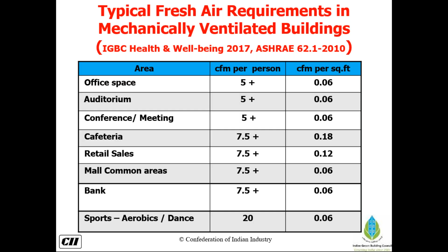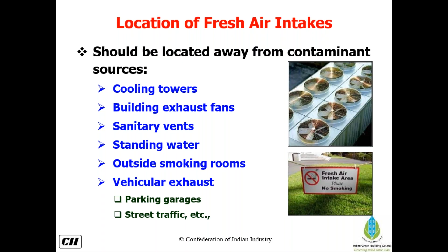We must ensure that we locate them away from all contaminating sources, such as cooling towers, exhaust fans, or smoking areas. And in case it's a space which has a smoking area, for example an airport, understand how we can make small rooms which are negatively pressurized, and how the exhaust pipes, the outlets, are placed away from the building and away from inlets.